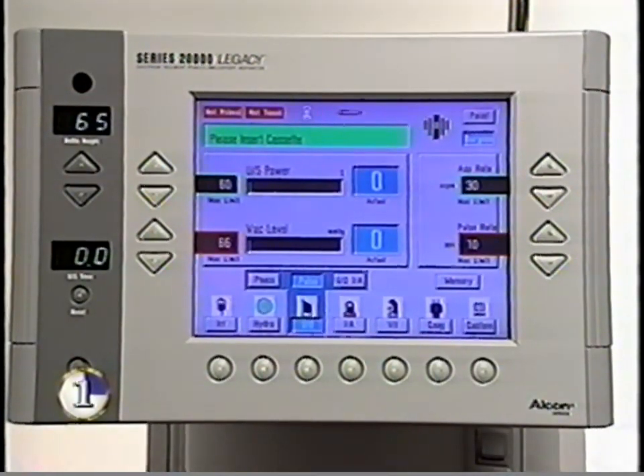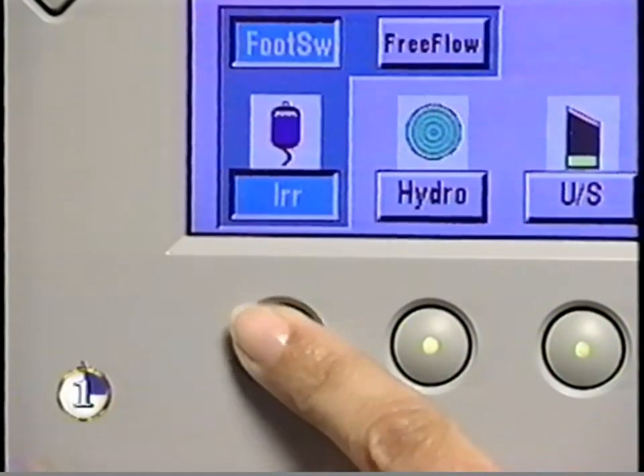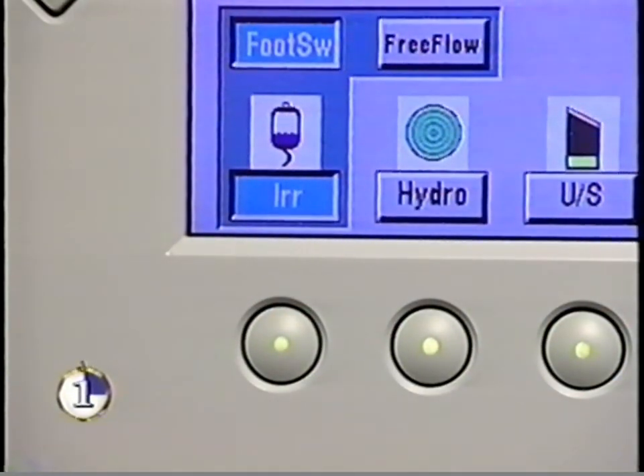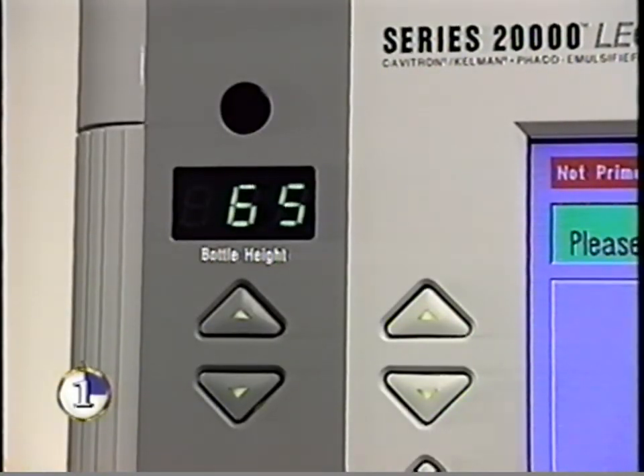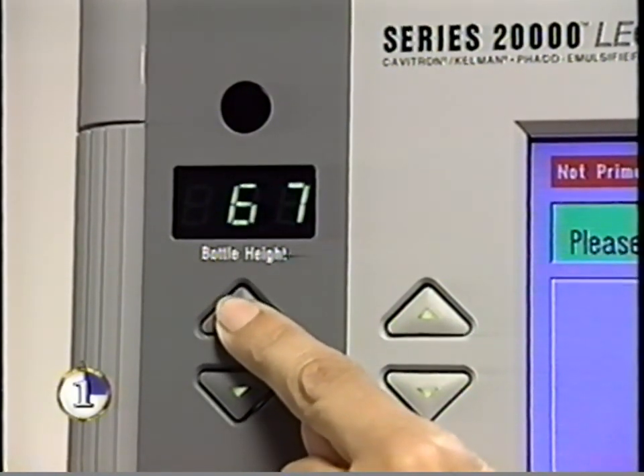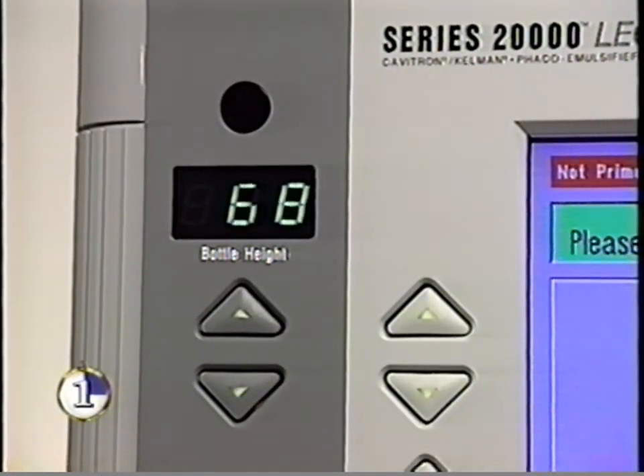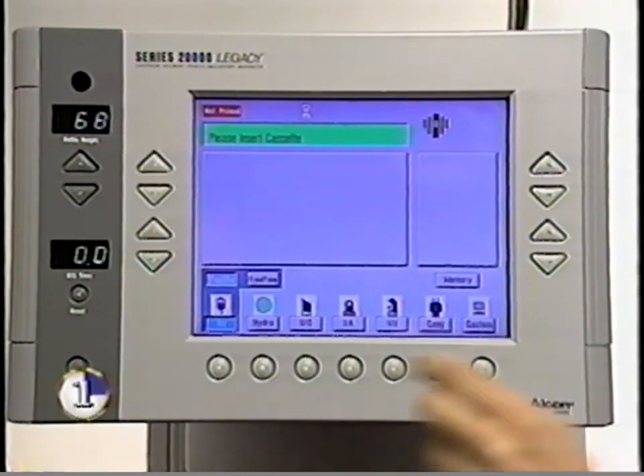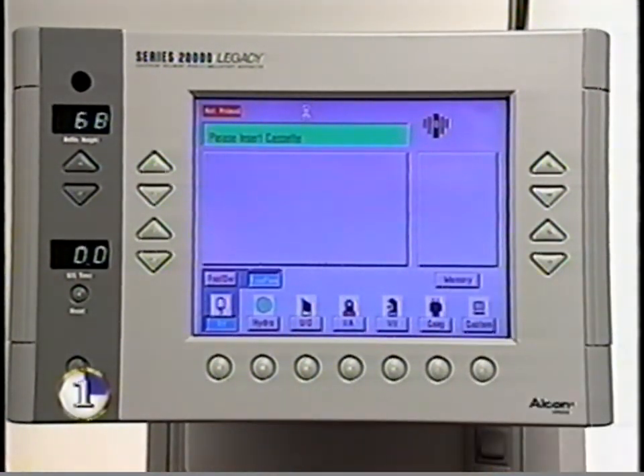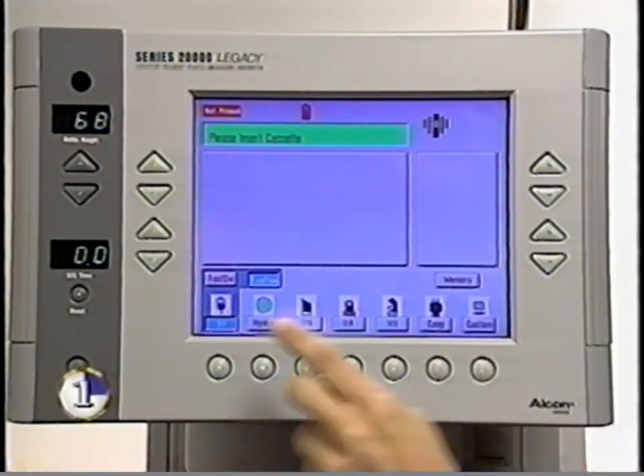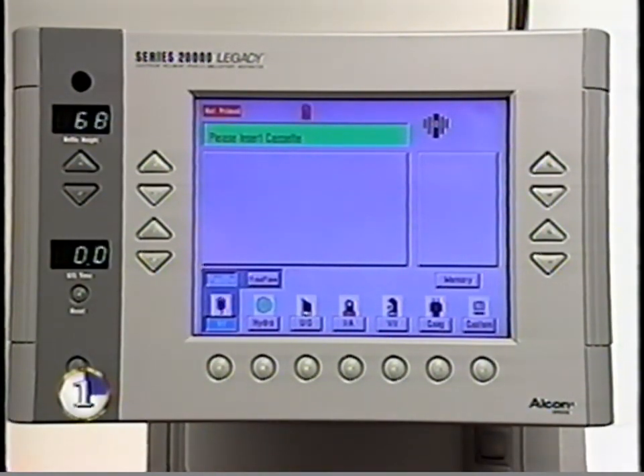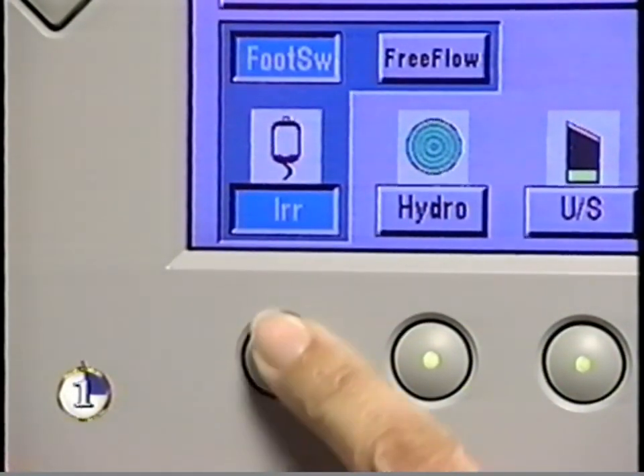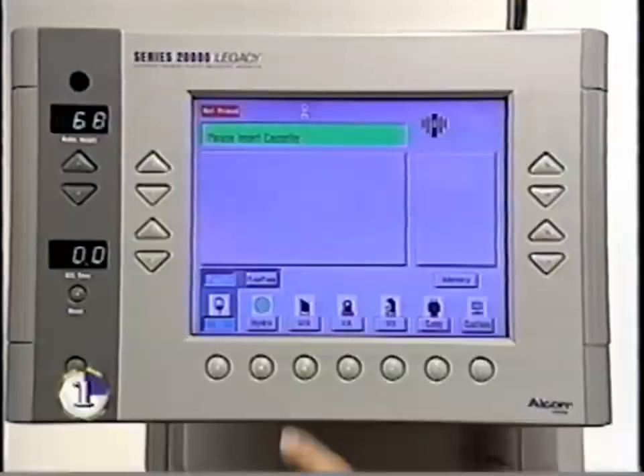Use the primary mode selection buttons to activate the irrigation mode, which provides gravity feed infusion into the eye. Adjust irrigation flow by raising or lowering the irrigation bottle. Press the irrigation button once to start constant fluid inflow. To stop irrigation, press it again. Irrigation foot switch is the system default setting.